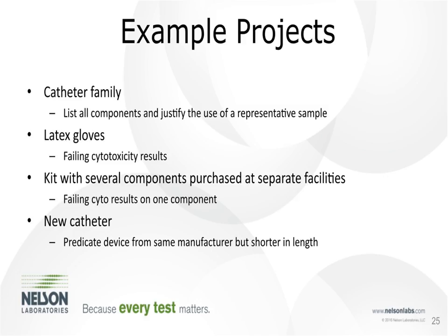We did a literature review, and we had known amounts, so we were able to do some calculations to determine the safety. Well, what we came up against, and Dr. Campbell talked about this yesterday, is that in that literature review, for one of those compounds, there was not enough published literature for us to fully assess its safety. So at that point, we had to go back and get some more data. We did some additional testing. And with that data, plus the literature review and passing results for the other biocompatibility tests, we were able to show that this device ended up being safe.